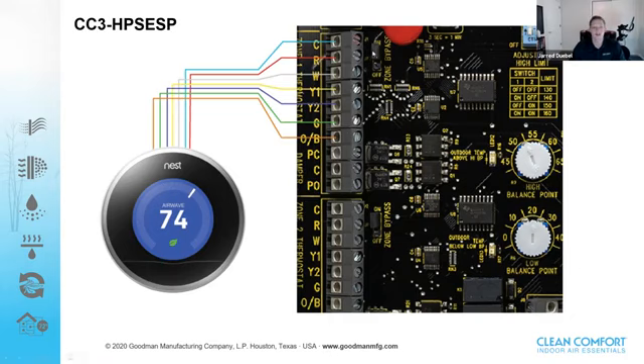All you've got to do is take this little jumper switch and pick it up. There are actually 2 pins here, and you can set it to the off position. And you can set it that way for any zone that you would like. So when you're using the ESP zone control system, any zone, so long as it has this little jumper set to the on position, is going to bypass air whenever we reach that static pressure threshold. But any zone you do not want that feature enabled on, you simply set to the off position.